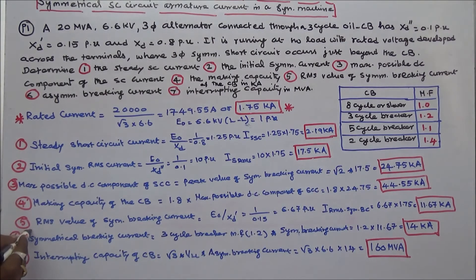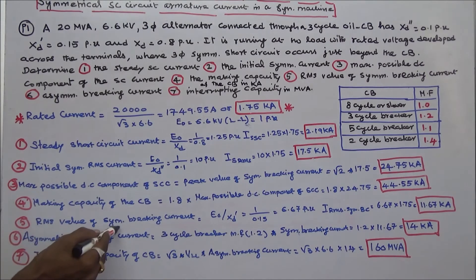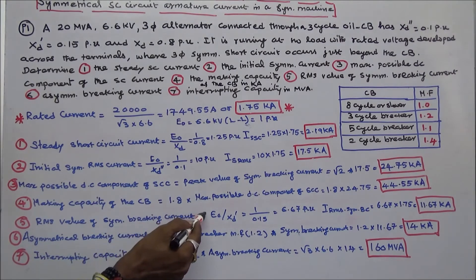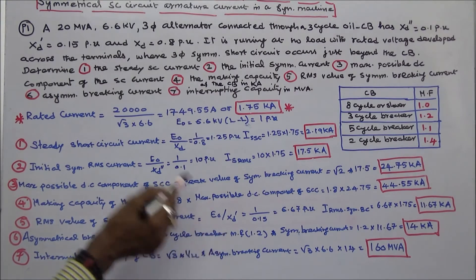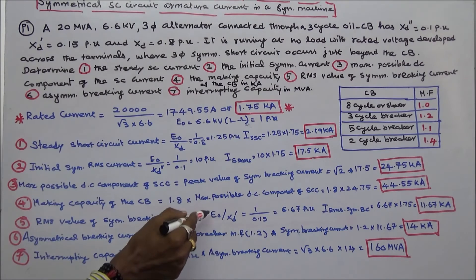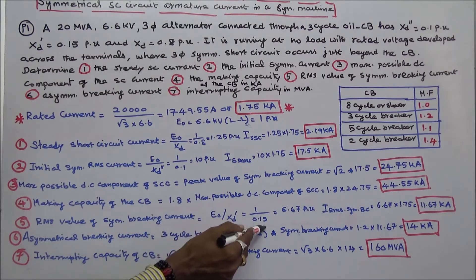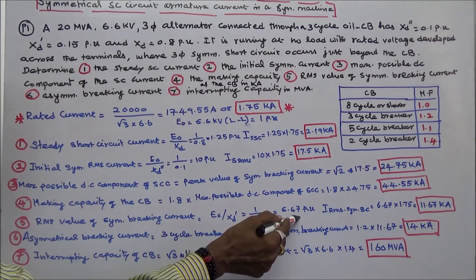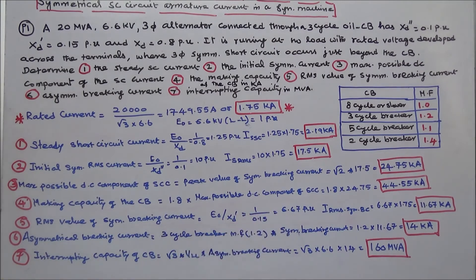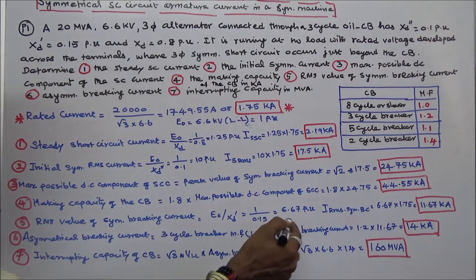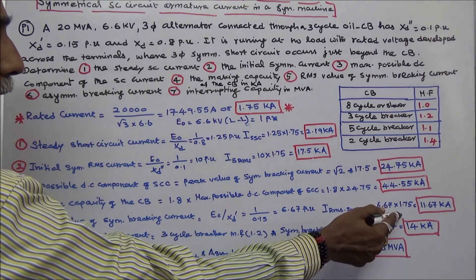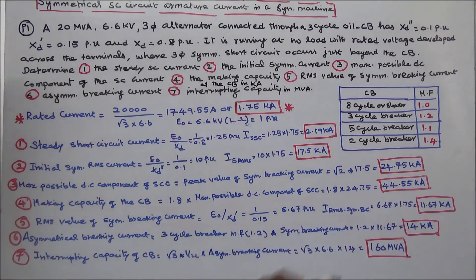Fifth is the RMS value of symmetrical breaking current. That equals E0 divided by transient reactance. Transient reactance is 0.15, E0 is 1, so 1 divided by 0.15 equals 6.67 per unit. Actual RMS value of symmetrical breaking current is 6.67 into 1.75, which equals 11.67 kA.